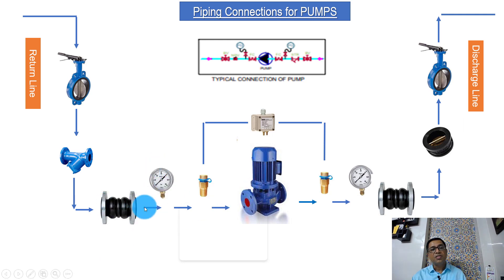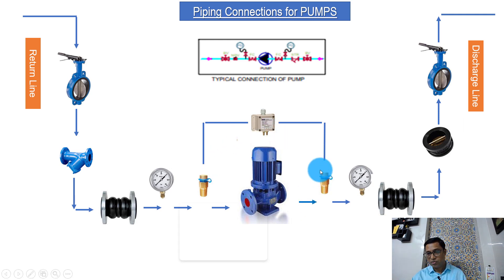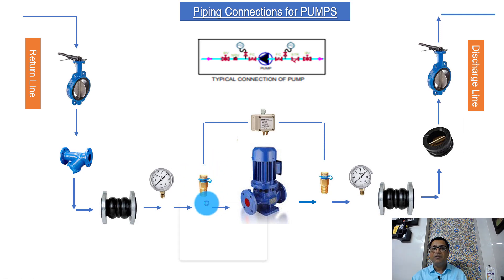These vibration flexible bellows, or flexible connections, reduce the vibration impact coming out of the pumps. Then we have a pressure gauge — we should know what the pressure is at this point near the pump. We also provide, depending on the installation, either a ball valve or a test point here, because we want to connect and get information related to differential pressure across the supply and return of the pumps. This DPT sends a signal to the BMS system, which is why it is important.